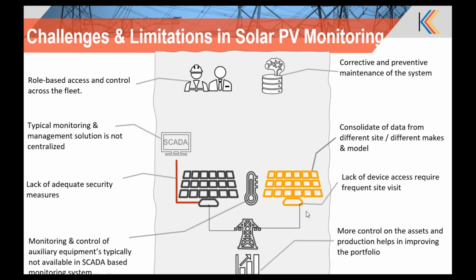SCADA also does not provide secure remote access to these devices. For example, with the arrival of DER and smart inverters, you could control volt-var to stabilize the distribution grid and improve power quality. That kind of var pumping can be done using inverters through remote settings, but those kinds of settings may not be possible from legacy SCADA systems.